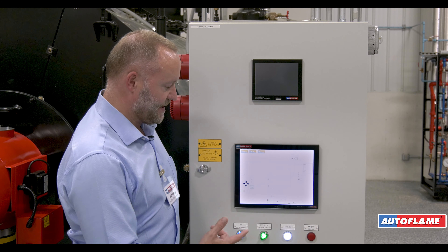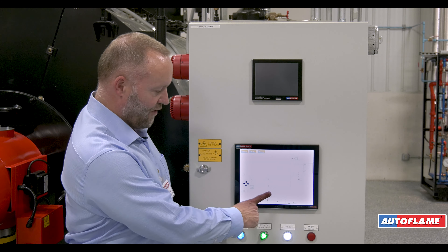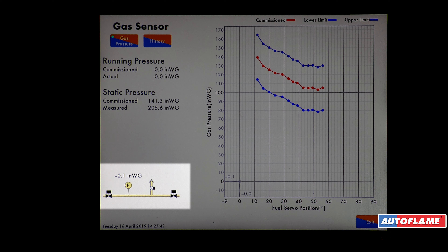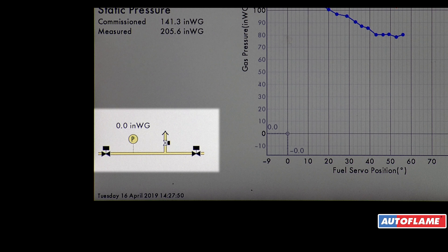Now the burner is going to go through a safe start. We start off with a relay test. Pressing on my gas train I can look at my gas valve setup. I've got two main gas valves and a vent valve and here's my pressure. First thing we're going to do is open the gas valve vent to zero the pressure between the two valves.